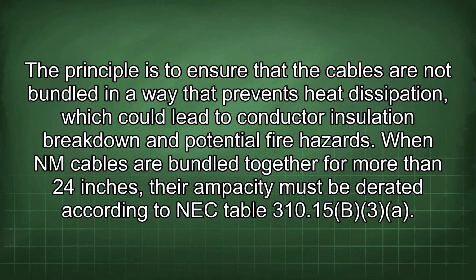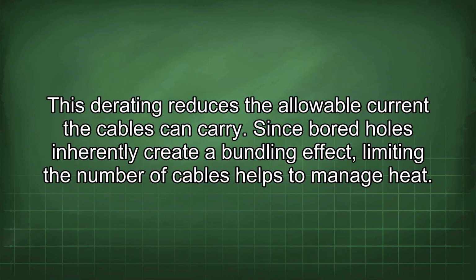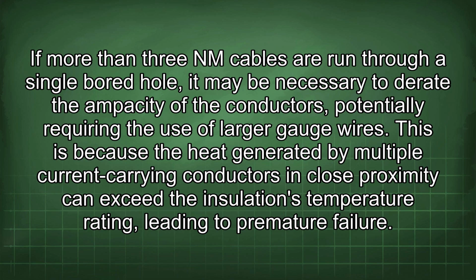When NM cables are bundled together for more than 24 inches, their ampacity must be derated according to NEC Table 310.15(B)(3). This derating reduces the allowable current the cables can carry. Since bored holes inherently create a bundling effect, limiting the number of cables helps to manage heat. If more than 3 NM cables are run through a single bored hole, it may be necessary to derate the ampacity of the conductors, potentially requiring the use of larger gauge wires.